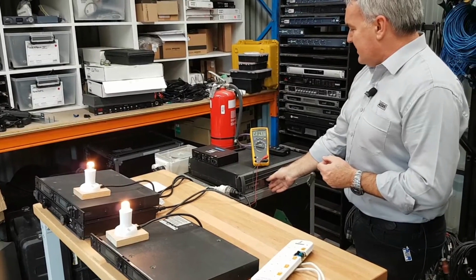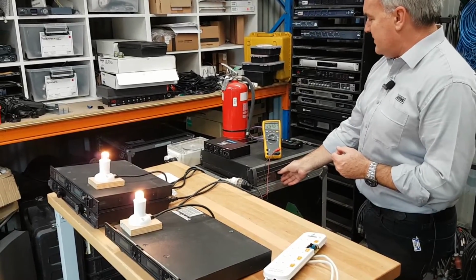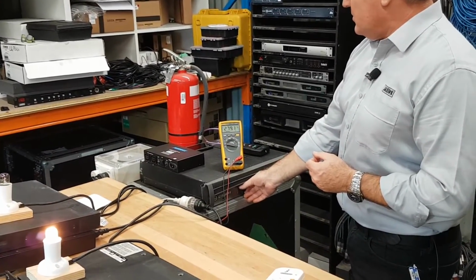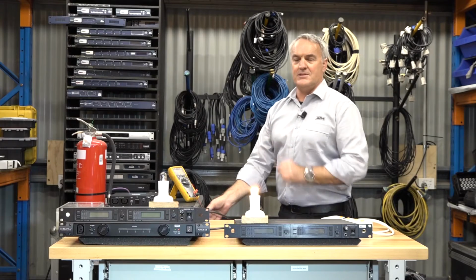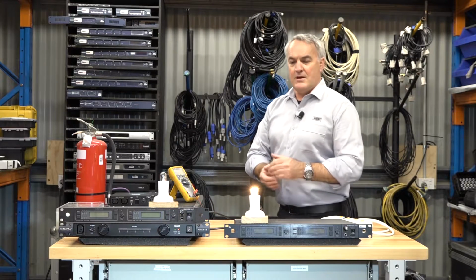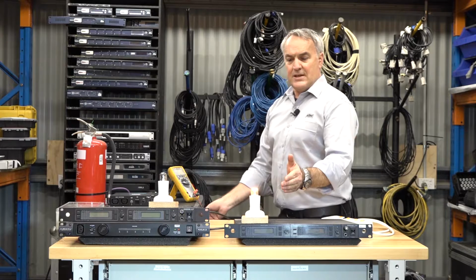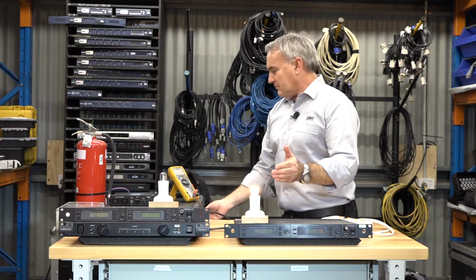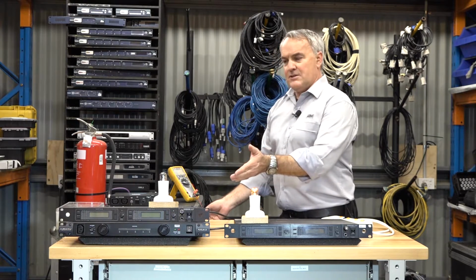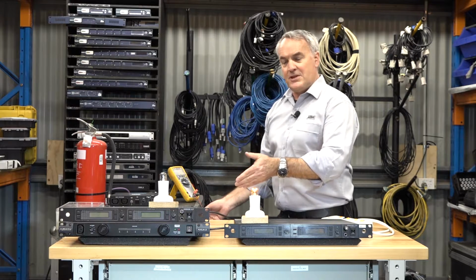So we'll just start to bring the mains up now. We're at 247, 260, 279. You see that the Furman has instantly protected that light bulb. This one's being exposed to the full extent of the mains over voltage event. When this happens, as you can see, the Furman remains isolated to protect your equipment.